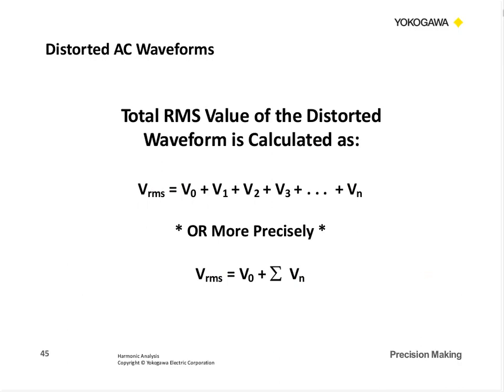And so the RMS value of the distorted waveform is calculated as the sum of the harmonics, okay? This is showing the integer harmonics. More precisely, it's the DC component plus the summation of all the harmonic orders.